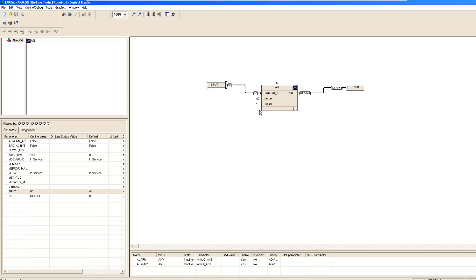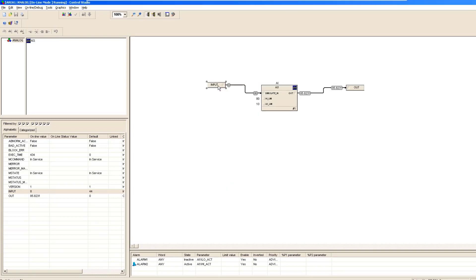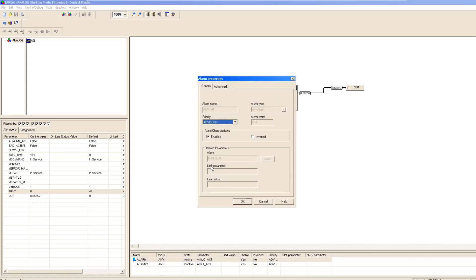For instance, I give it a value of 86, which is more than 80. You will see it slowly changing because of the PVF time. When the value exceeds 80, a High Alarm is activated. Now if I give a value less than 10 — for instance 8 — it will slowly get back to 8, and when it reaches less than 10, the Low Alarm is activated. You can see the Low Alarm has been activated here.